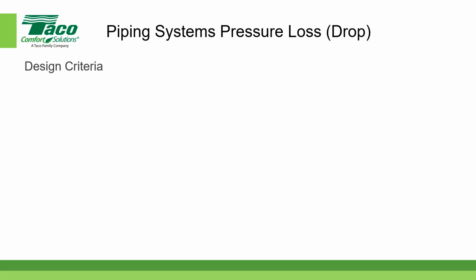Well, whenever we do a pressure drop calculation, we need to define some parameters. And most of the time, it's done as sort of an office standard. So in this particular case, we are going to set some very basic criteria. We're going to say that for our manual design we're going to have a maximum velocity of 8 feet per second. And we're going to have a maximum pressure drop of 4 feet per 100 feet of pipe. So those are our criteria.